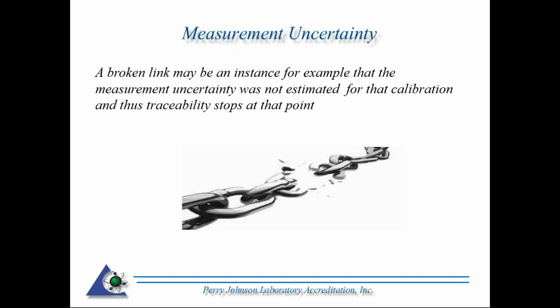That's why it's important when we're doing assessments, particularly of calibration labs, that we look at specifying measurement uncertainty. We're looking at your uncertainty. We're looking at where your standards were calibrated. We're looking at the uncertainty from there and seeing if, in fact, your uncertainty builds upon the uncertainty of the lab that you received your calibration from.